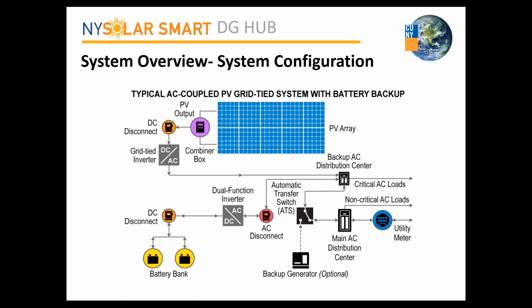Next slide. In the next slide, we look at the AC coupled system, where you keep the grid-tied inverter intact and then add the battery bank and the AC-DC dual functioning inverter, all tied to the backup AC distribution center. The utility will be charging the batteries, and when the utility goes down, you'd have either a backup generator or the PV system charging the batteries. In this system, it's a little less efficient because the PV output is converted to AC by the inverter, and then you have to go back through an AC to DC conversion to charge the batteries when you're in off-grid mode. So it's slightly less efficient, but it's often more acceptable in a third-party situation where you already have an inverter and an ownership.